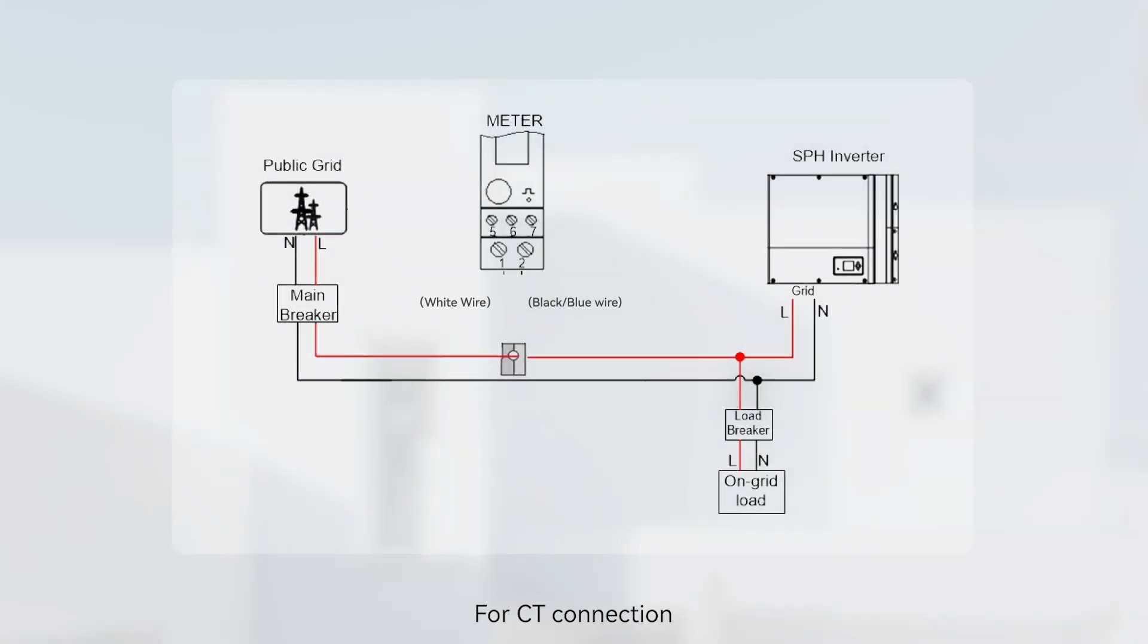For CT connection, connect the white wire and black wire of the CT to port 1 and port 2 of the smart meter. Then, put the CT across the live line of the grid, which is after the main breaker and before the load. Make sure the arrow of the CT points from grid to the load.